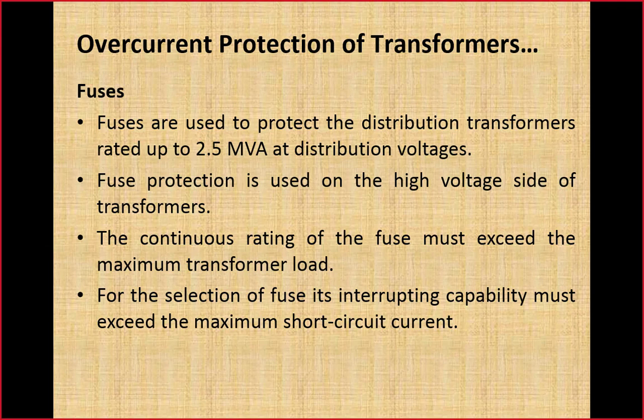Repeating it again, the fuse continuous rated current should be greater than the maximum possible load current of the transformer. Second, the interrupting capability of the fuse should be greater than the maximum possible fault current. Further, when we energize a transformer, it draws a very high current known as inrush current. These fuses should be capable of withstanding that inrush current without blowing as well.